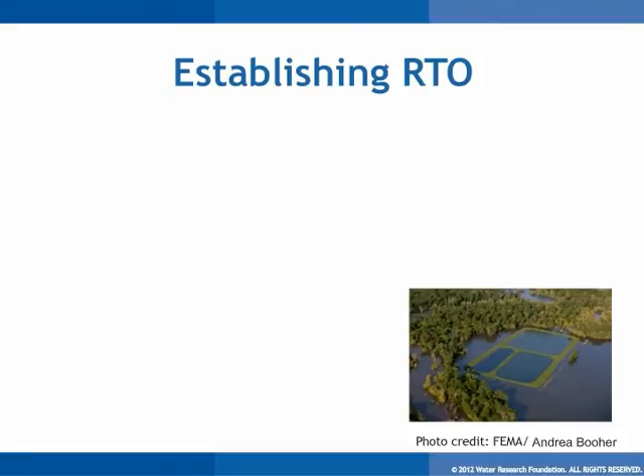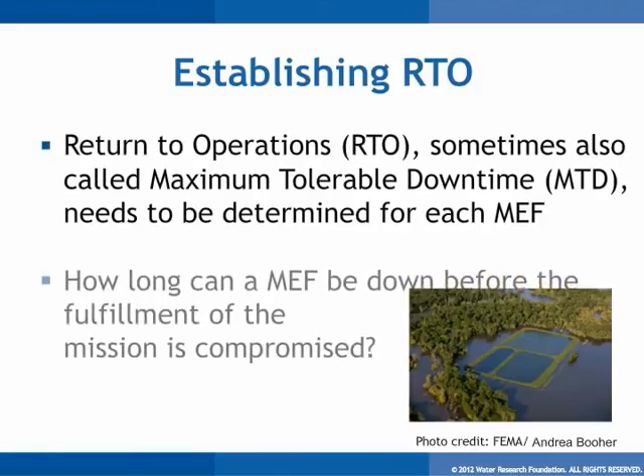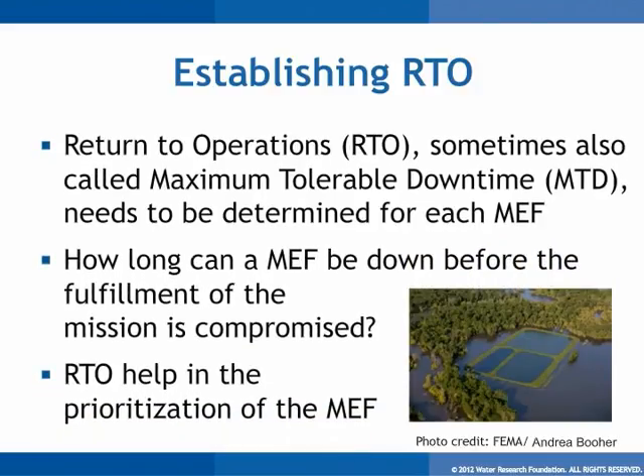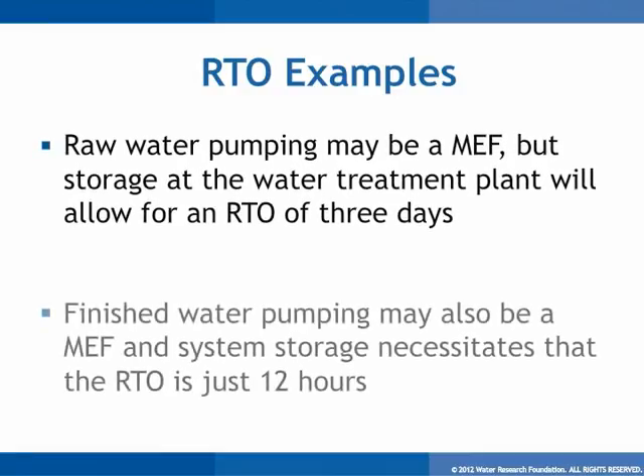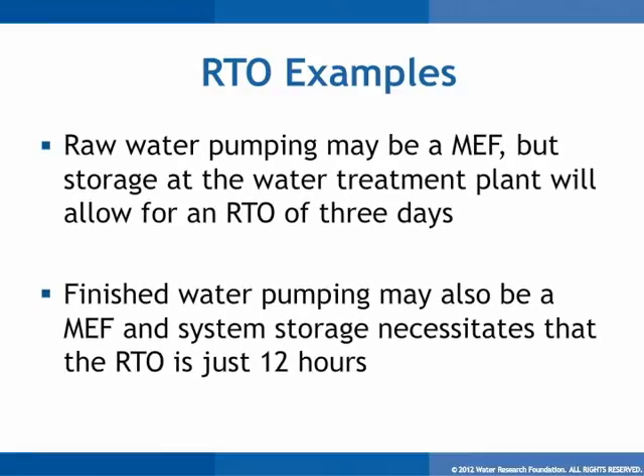An important step in the identification and prioritization of MEFs is the establishment of the time for return to operations for each MEF, sometimes referred to as maximum tolerable downtime. While all MEFs may need to be recovered within the 30-day BCP timeframe, some are needed more urgently than others. For instance, if the utility has several days of raw water storage at their water treatment plant, the RTO for raw water pumping may be three days. If, however, they have only about 12 hours of finished water storage, the RTO for finished water pumping might be more on the order of 12 hours. In this example, while both forms of pumping are MEFs, the RTO for the finished water is shorter, so finished water pumping would likely receive a higher prioritization.